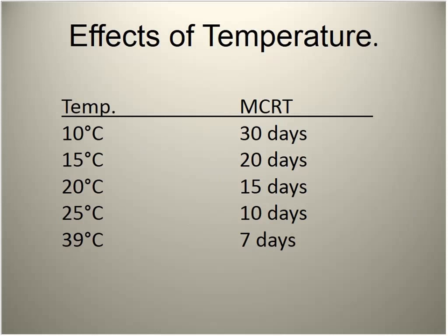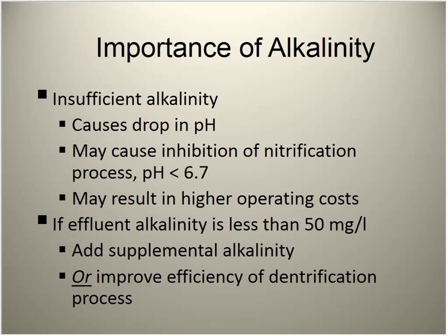At 10°C, developing the proper organisms to nitrify could take about 30 days MCRT. Facilities that don't maintain nitrification through winter will start adjusting their process in March to be ready for April limits — it takes 15–20 days to get started. Alkalinity is a critical parameter that often gets overlooked. A drop in pH below 6.7 will start to inhibit the process, so at least 50 mg/L of alkalinity must remain at the end of the reactor.